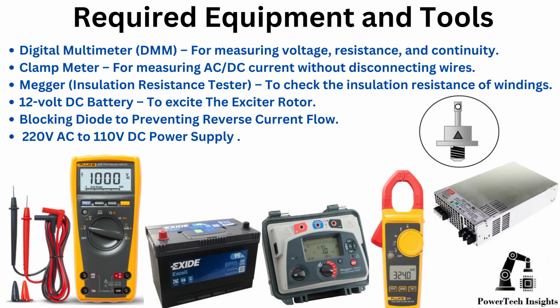Required equipment and tools. Digital multimeter for measuring voltage, resistance, and continuity. Clamp meter for measuring AC/DC current without disconnecting wires. Megger to check the insulation resistance of windings. 12-volt DC battery to excite the exciter rotor. Blocking diode to prevent reverse current flow. 220V AC to 110V DC power supply.